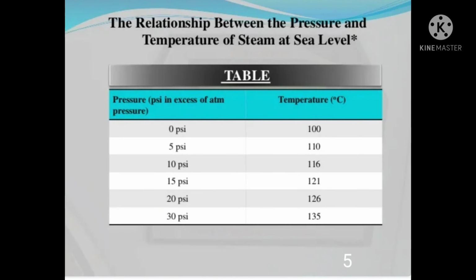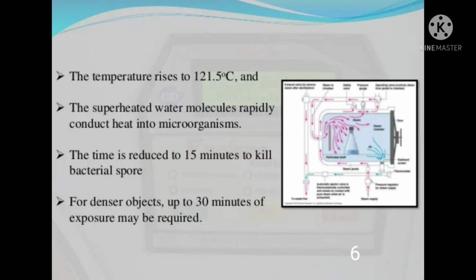There is a relation between pressure and temperature of steam at sea level. When there is zero difference above the atmospheric pressure, the temperature required for boiling water is 100 degrees centigrade. That is, as we all know, the boiling point of water is 100 degrees Celsius. But at a pressure of 15 psi, a temperature of 121 degrees centigrade is required to boil the water. This is exactly the temperature required to kill all microbial spores and to ensure complete autoclaving or sterilization. So this is exactly what happens during autoclaving.